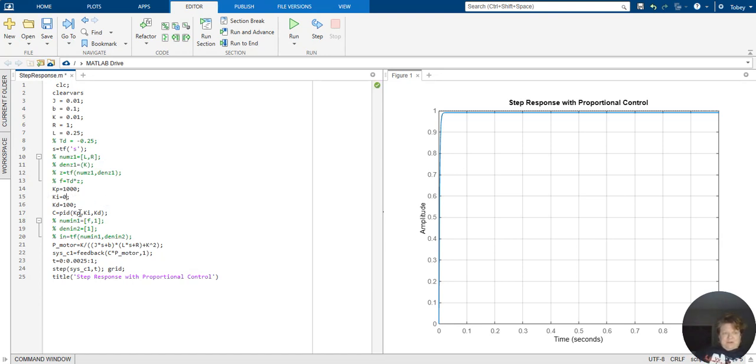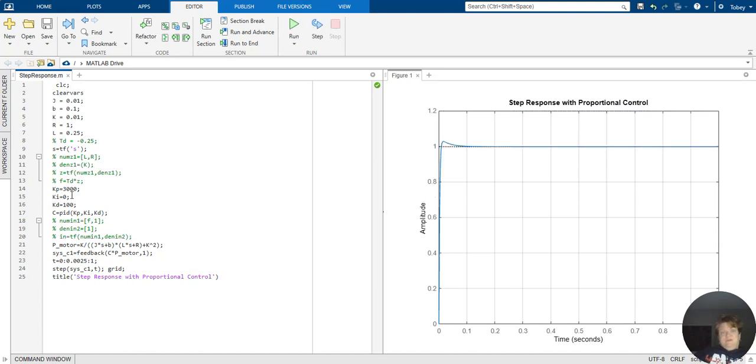Interesting. So proportional integral and derivative. Most of the time we don't even use a derivative, depending on what kind of loop it is. And obviously if I get too high on proportional at all, it's going to keep just, it won't go any higher. It's balanced like that.